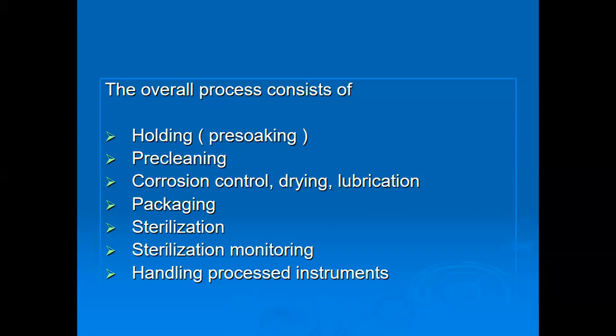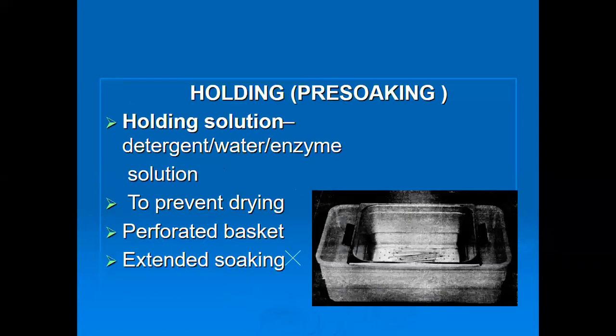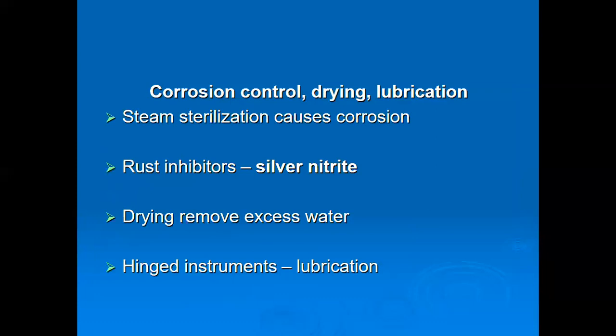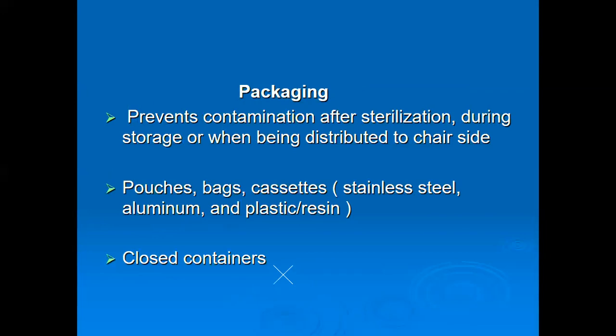How do you monitor sterilization? This is how, okay, we'll go into it. But then you have got holding, which means to prevent drying, you can use a bucket or something, detergent and all, just pre-soak. Pre-cleaning, ultrasonic cleansers are there. Corrosion control. Packing prevents contamination, so you need to take care of the packing also.